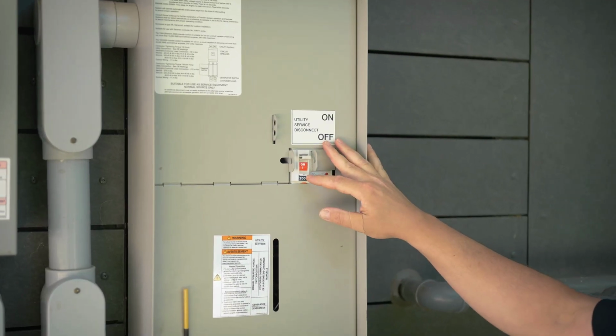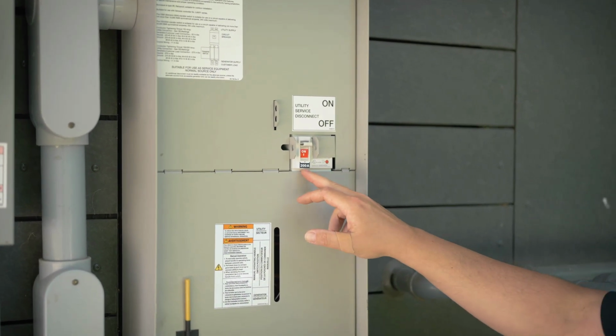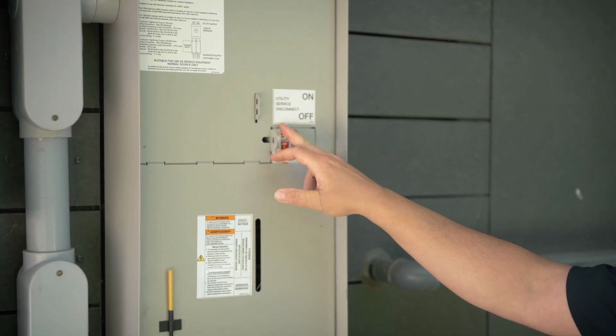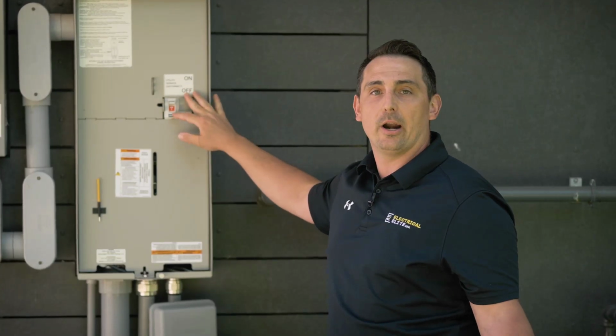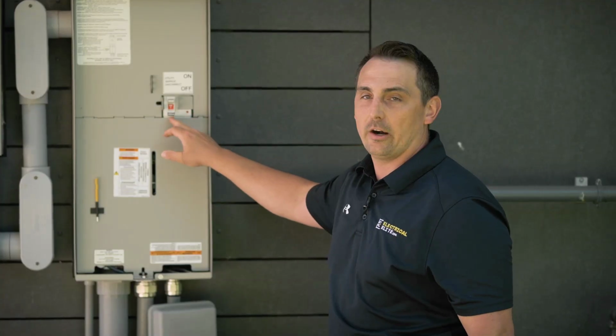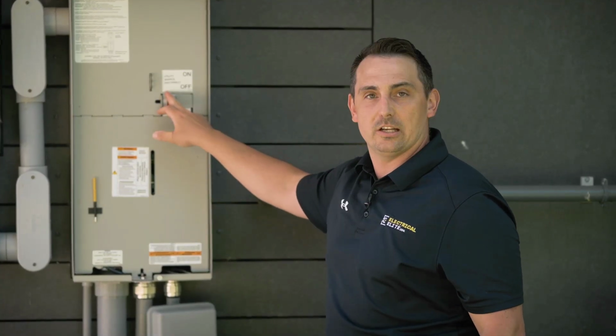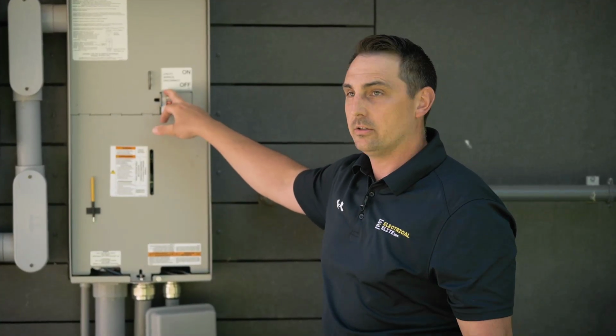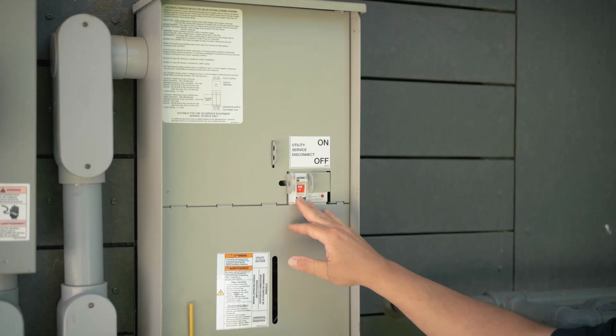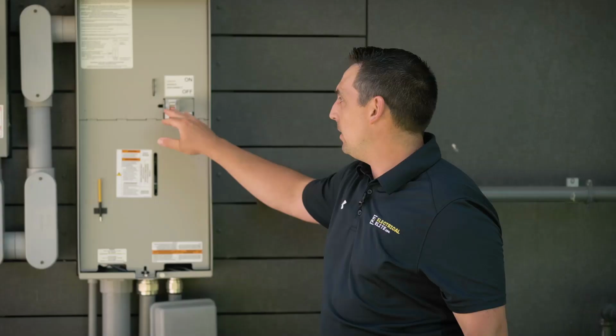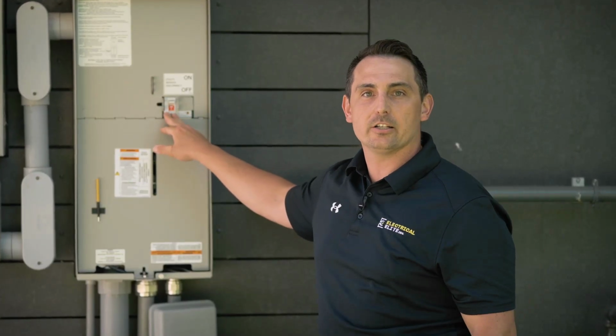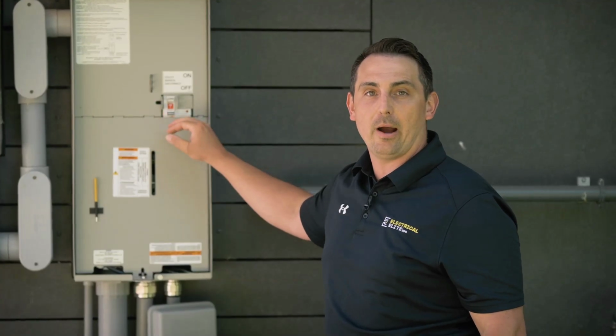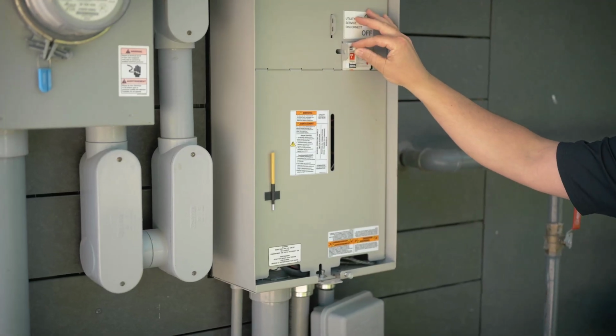Here is the mainline circuit breaker. Similar to your house, it has a main breaker. This is also a main breaker for this home. It's 200 amp rated and can be used as a shutoff for the entire house. This shutoff can also be used to simulate a power outage. If you wanted to test your generator system, you can do it by yourself by operating this breaker.